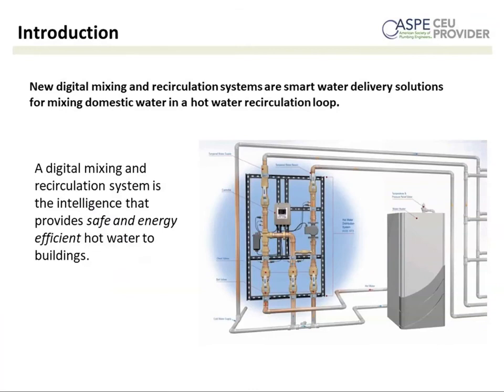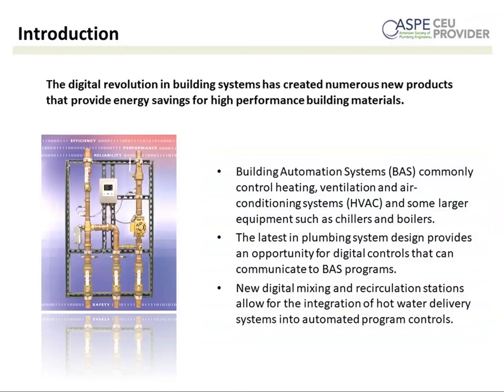So let's look at this digital mixing and recirculation loop, and this is part of it. It's representative of your hot water source and a station, okay? In this particular case, this is a digital mixing system, and you're managing essentially your mixed outlet temperature, and you're able to monitor and manage your return temperature as well. The hot water source, typically when you're using 2-temperature hot water, is where digital mixing is ideal.